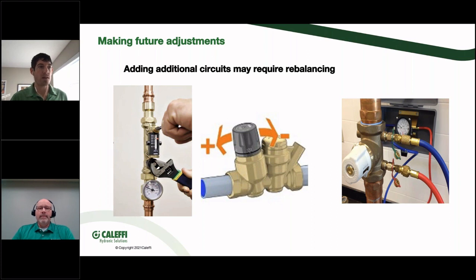Yeah, and I would say that if you were doing any sort of retrofit, adding a manual balancing valve is going to be potentially the trickiest, where we've had a couple projects that were never really balanced to start with. To go back with a thermal or a direct reading is much easier if you don't 100% know where everything's going. You can just say, okay, this riser needs 120 degrees, period, and we don't have to go back through everything. So that's definitely retrofit friendly. Yeah, absolutely.